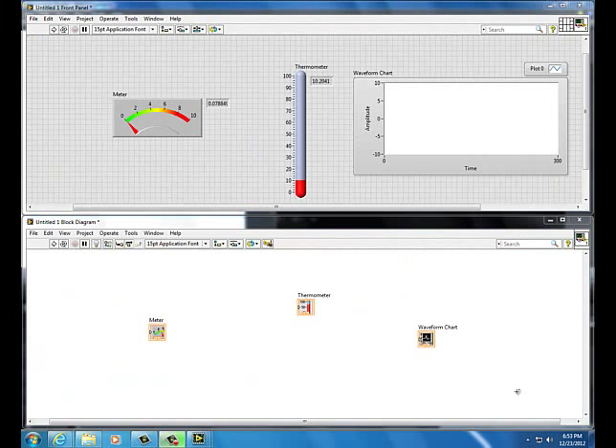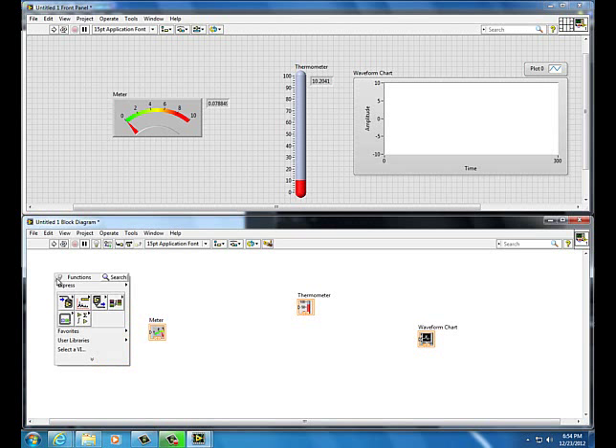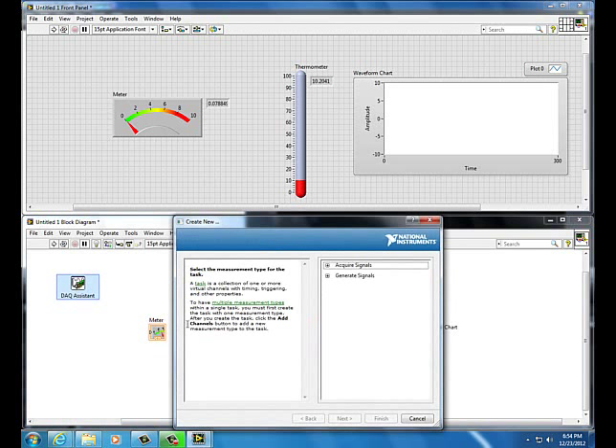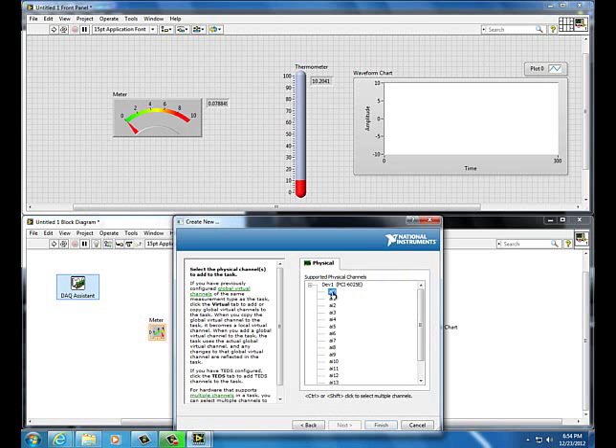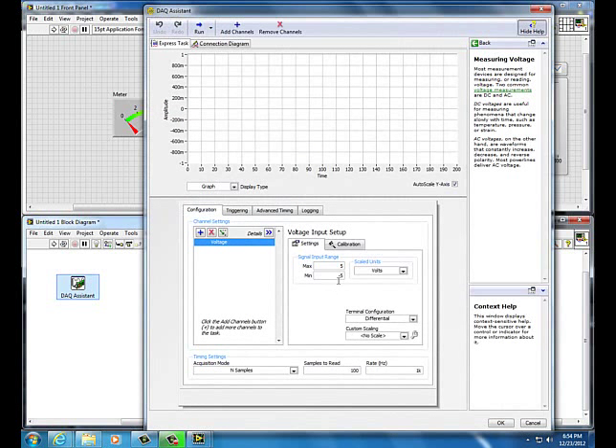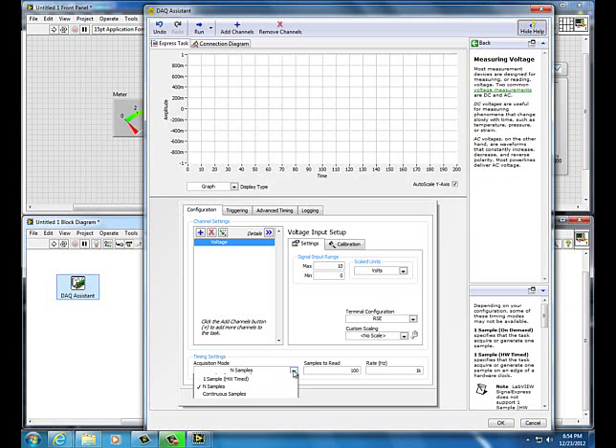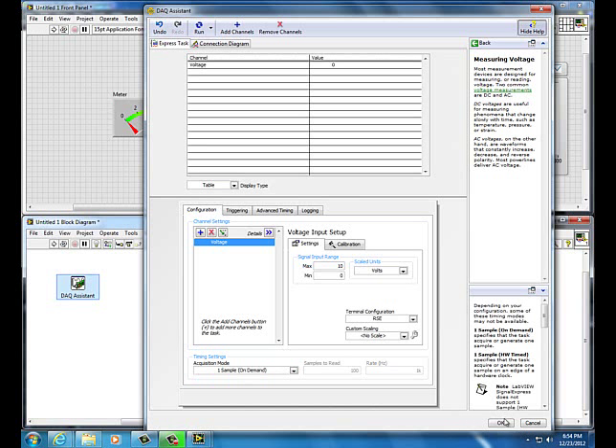Add a DAQ Assistant on the block diagram. First, notice that there are three icons already on the block diagram corresponding to the three icons added on the front panel. Right-click the block diagram, Express, DAQ Assistant, click it, drop it. Configure it: Acquire Signal, Analog Input, Voltage, Analog Input Channel Zero, Finish. Set maximum to 10 volts, minimum to zero volts. RSE stands for Reference Single-Ended. Set Acquisition Mode to One Sample On Demand, then click OK.